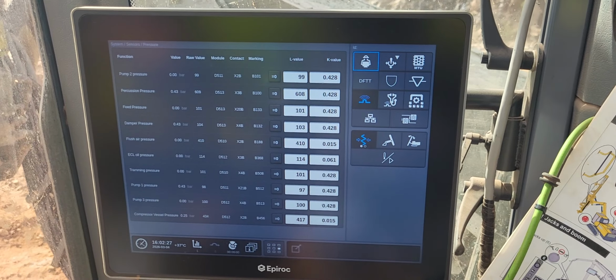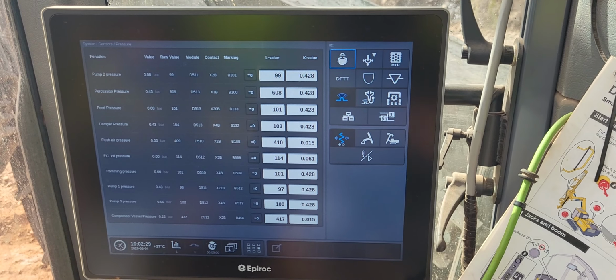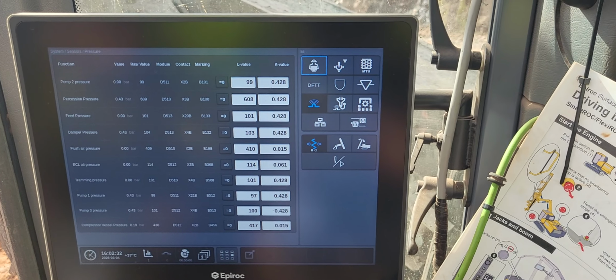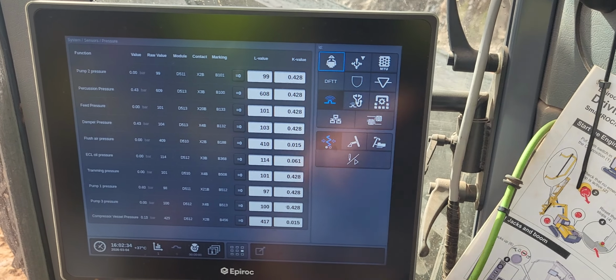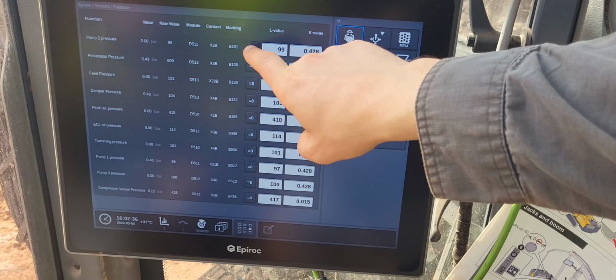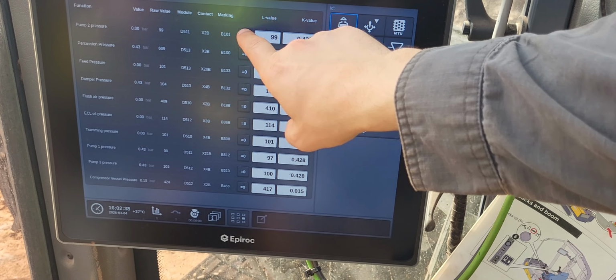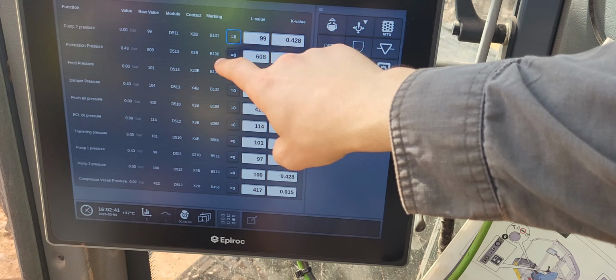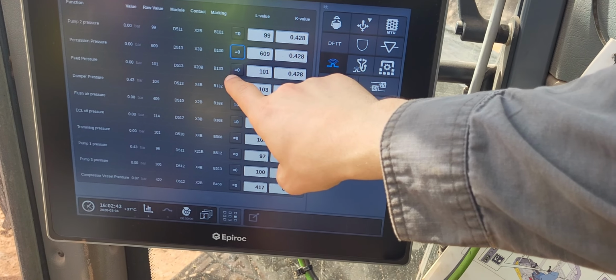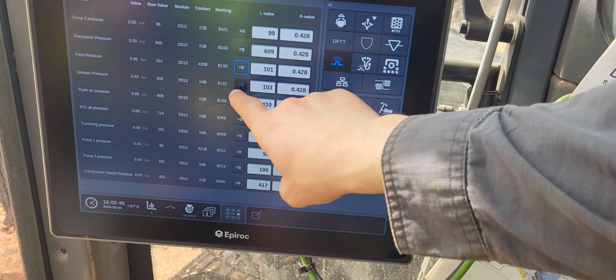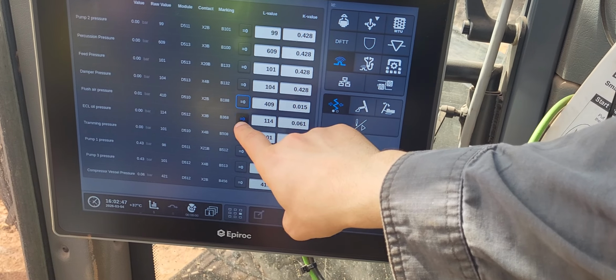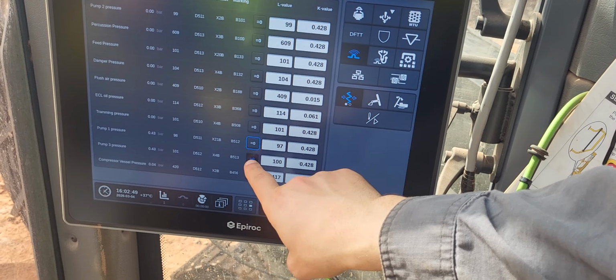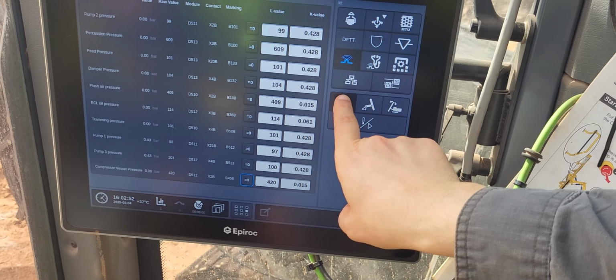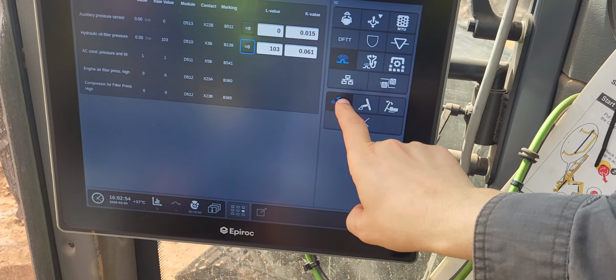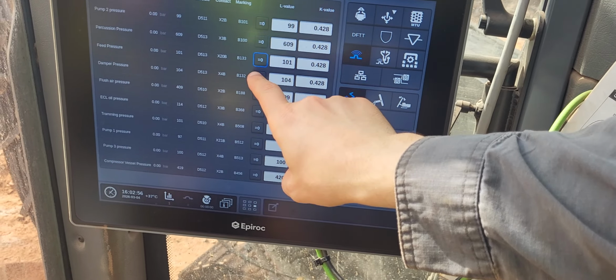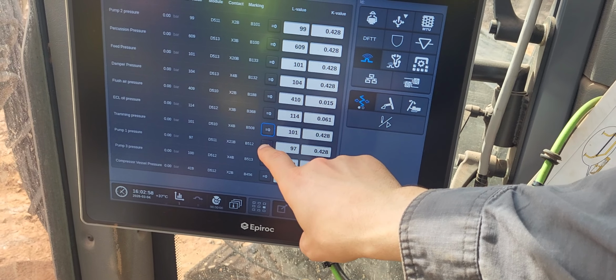So, for example, now is enough. Once we have like 2-3 minutes, it's gonna be enough. So what we start to do is that we just need to press the equal 0. So then the machine automatically makes the reset of the sensors. 0, 0, 0, 0. Okay. Very good. And if you do it 2 times, it's no problem.